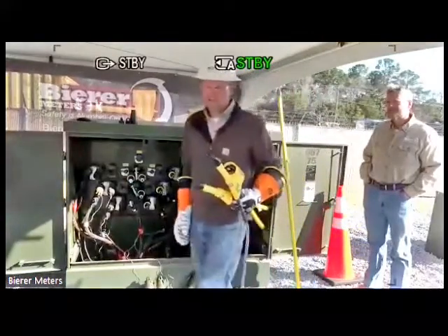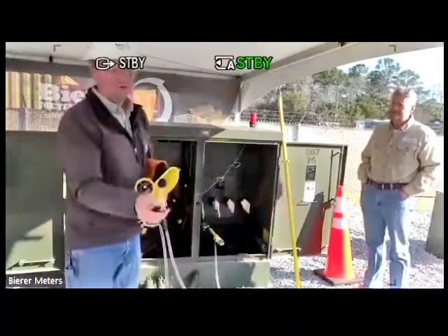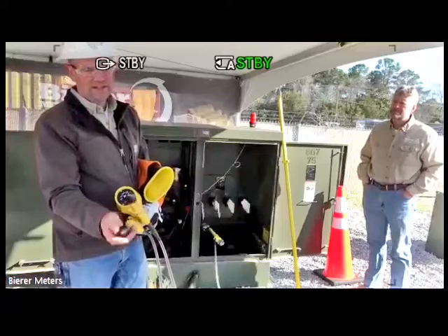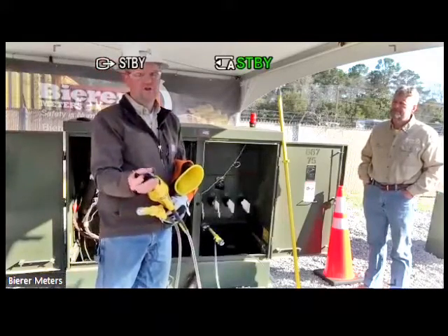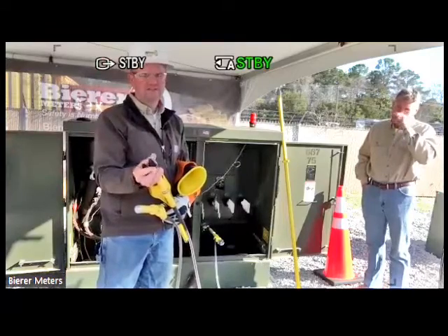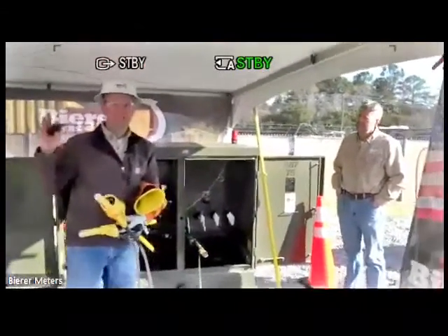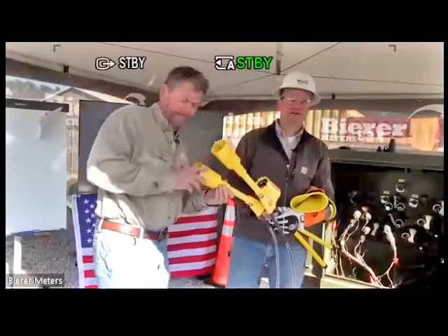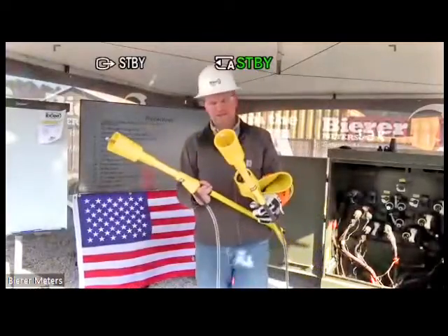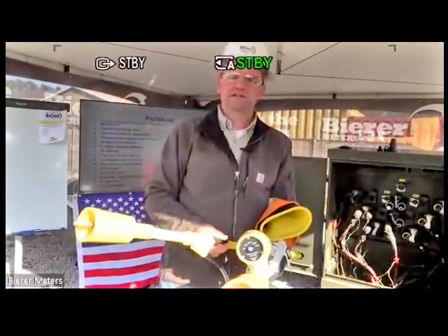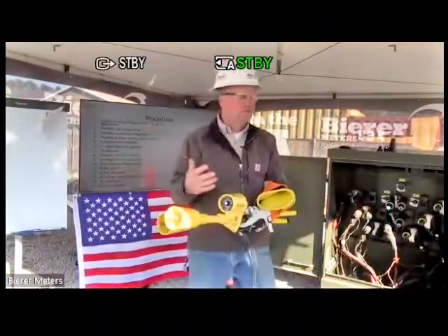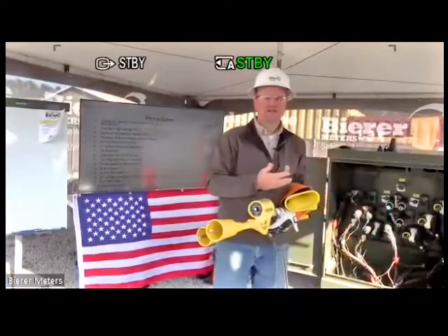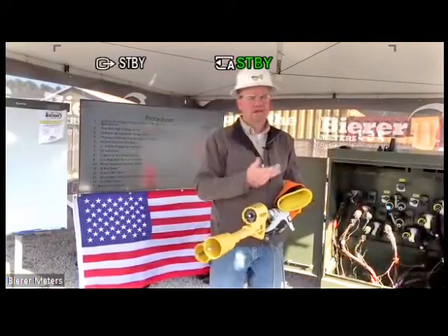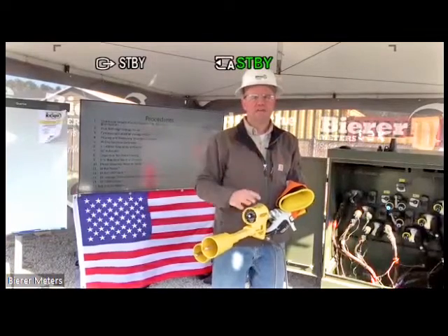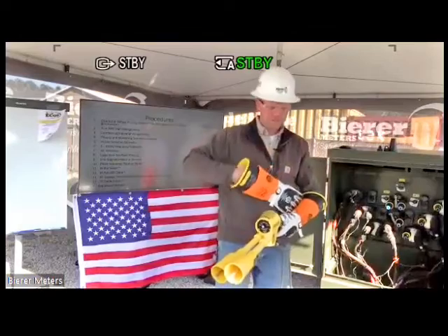Now on primaries, again, we mentioned a moment ago, this is where this tool really stands out, because there's no other device that will do that. As far as a traditional phasing meter, there's no other device where you can do your phase sequencing on primary conductors. Just to demonstrate that you can do it, it's not going to hurt the device. I'm actually going to leave this in the 2 kV switch position. Let's just say that, again, I'm a utility lineman. I came out here, did phase sequence on my secondaries. I forgot to change the switch, but I went ahead and put it in these primary bushings. What's going to happen to the device? I'm going to leave it in the 2 kV switch position. So let's see what happens to the tool when I do that.